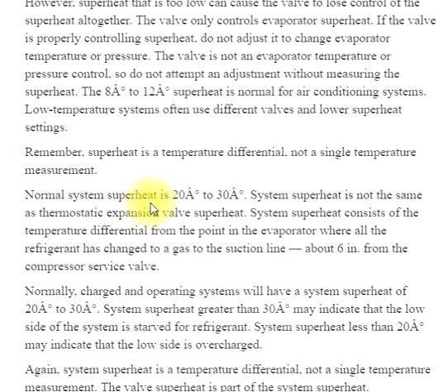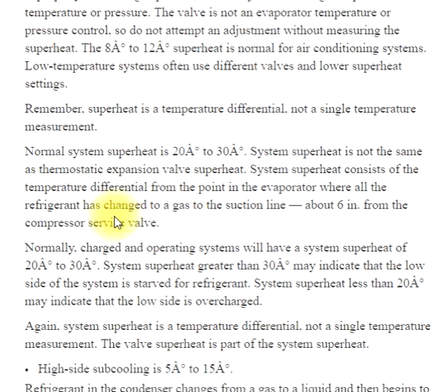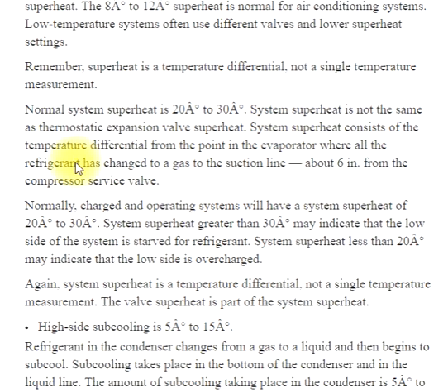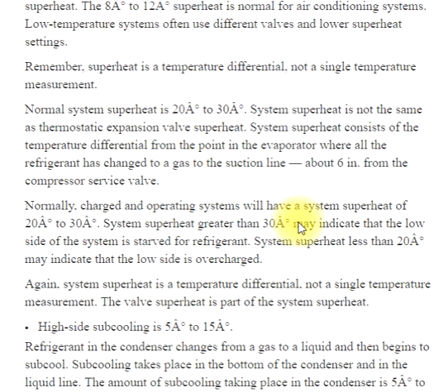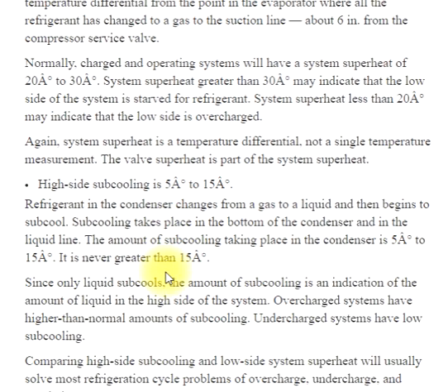Normal system superheat is 20° to 30°. System superheat is not the same as thermostatic expansion valve superheat. System superheat consists of the temperature differential from the point in the evaporator where all the refrigerant has changed to a gas, to the suction line about 6 inches from the compressor service valve. Normally charged, operating systems will have a system superheat of 20° to 30°. System superheat greater than 30° may indicate the low side is starved for refrigerant. Again, system superheat is a temperature differential, not a single temperature measurement. The valve superheat is part of the system superheat.